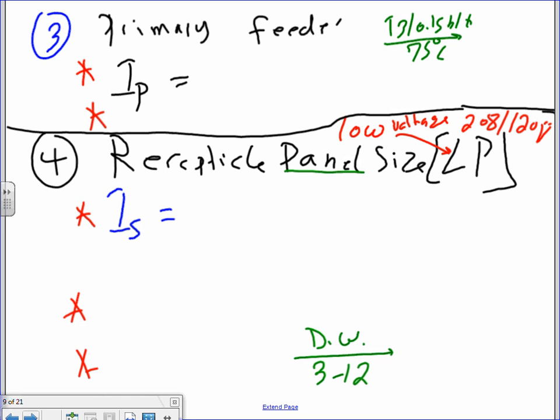90.2 amps. Then for feeder, we multiplied by 1.25, right? Primary feeder. 1.25 multiply 90.2. Who's my calculator? Two people. 112.75. If they take 112.8 amps, take it to 240.6. I need two people, guys, here to help me with that. Take it to the wall. Take it to 310.15(B)(16).